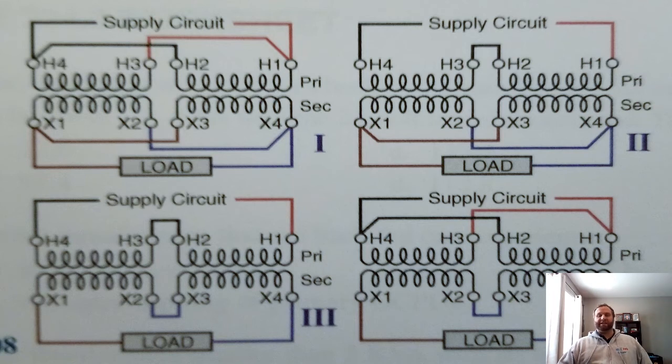When it comes to isolating transformers, remember these are dual voltage primary and dual voltage secondary transformers. You'll note that H4 and H3 is across from X1 and X2. Remember we talked about additive polarity. These windings in buck boost transformers are wound for additive polarity.